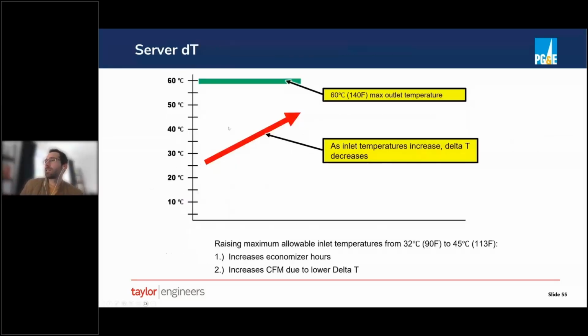All right, this is also something Jeff talked about a little bit earlier, which is that as the inlet temperature going into the servers rises, what we see is a decrease in the IT delta T. And so think about it this way. We have a server that has a fan inside of it. That fan is being controlled to maintain physical chip temperatures. And obviously, as we send warmer air into the server, the amount of air that's needed to maintain those chip temperatures tends to rise. So that internal server fan speeds up using a PID loop or some other fuzzy logic algorithm that the server manufacturer has programmed. So we see this reduction in delta T as we raise our entering dry bulb temperature to the servers, and that in turn has an impact on how we design our air cycle, right?